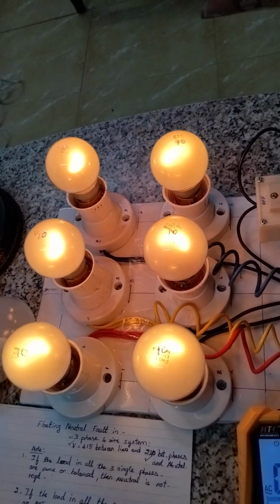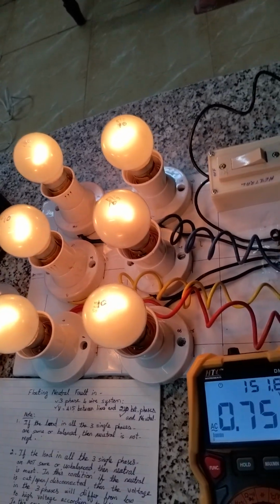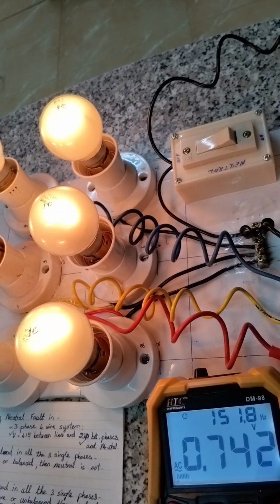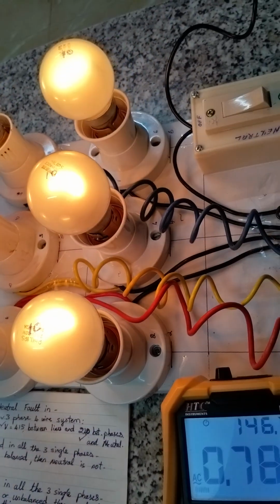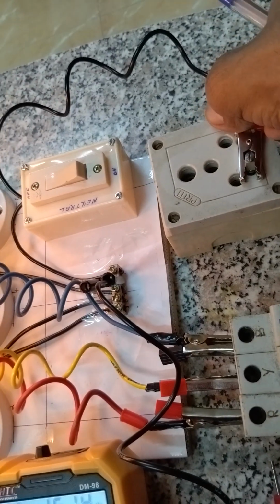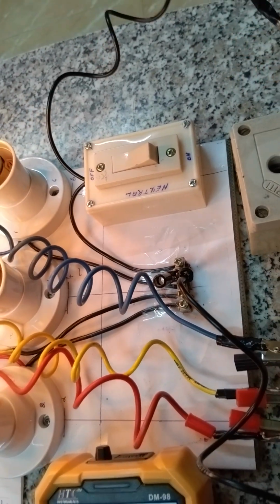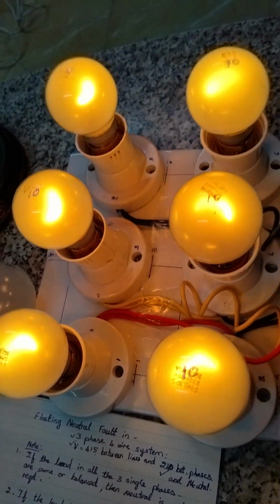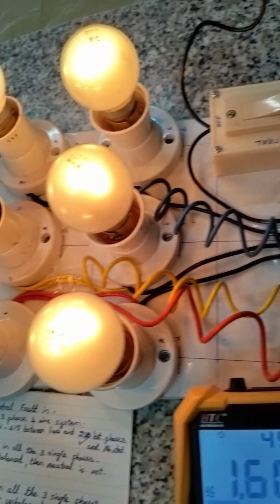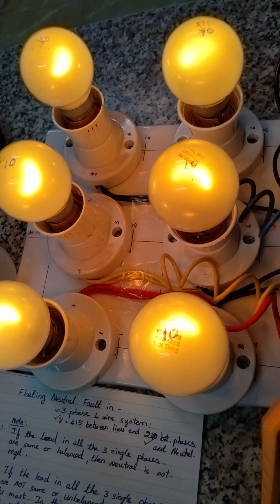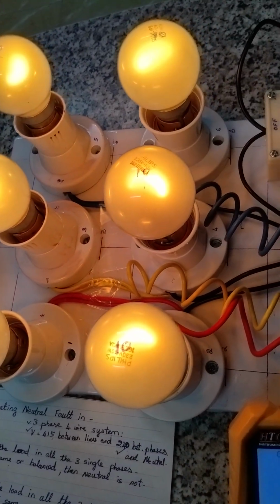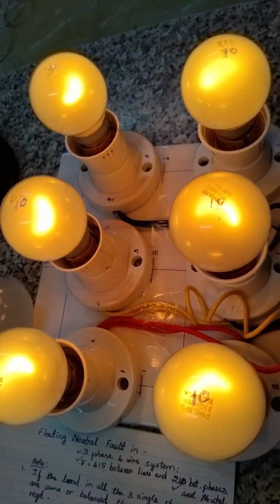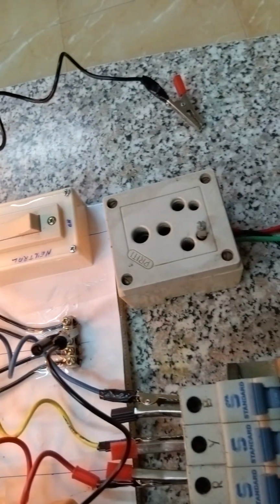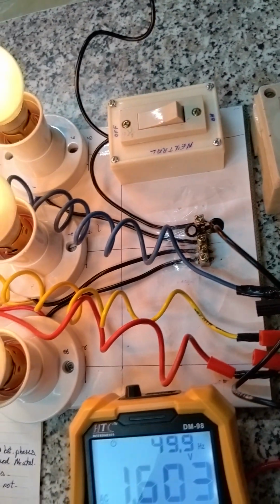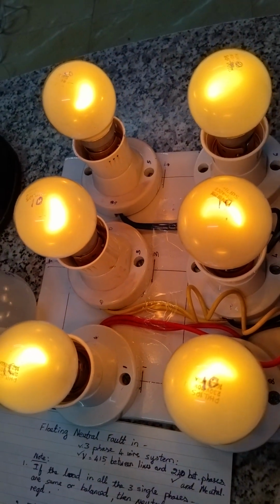Okay. Now I will just switch off the neutral. The neutral is switched off. That means the neutral has been disconnected. Even here I will show you. See, it is disconnected. No neutral. That's no problem. There's no need for a return path for carrying the return current. Please note carefully. You can see all the bulbs are lit.